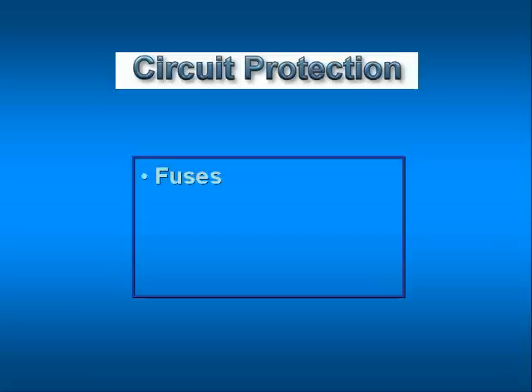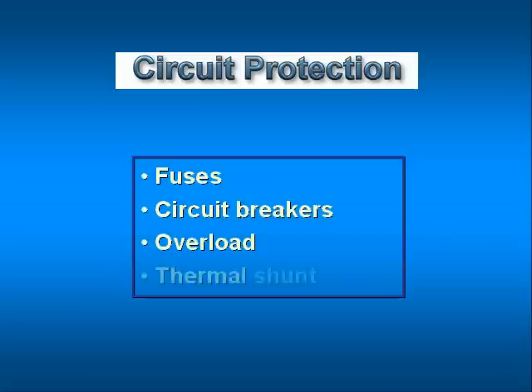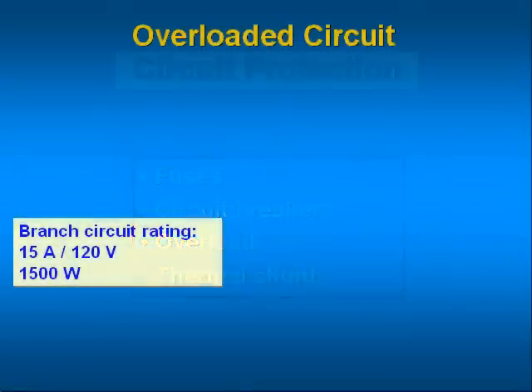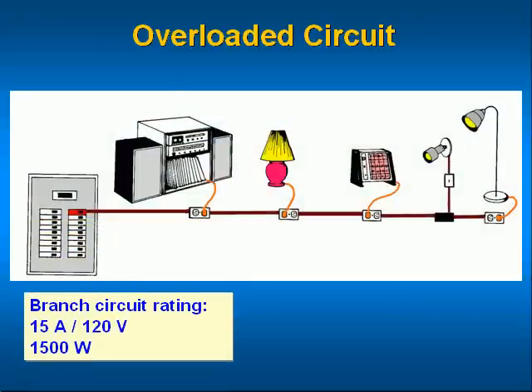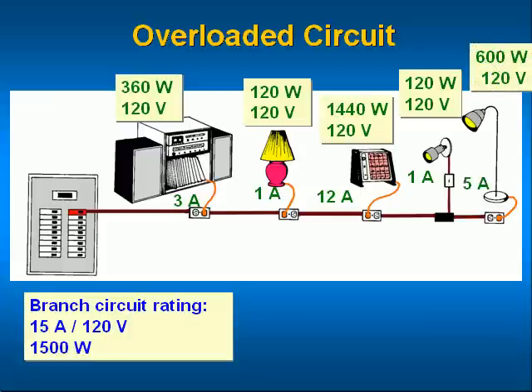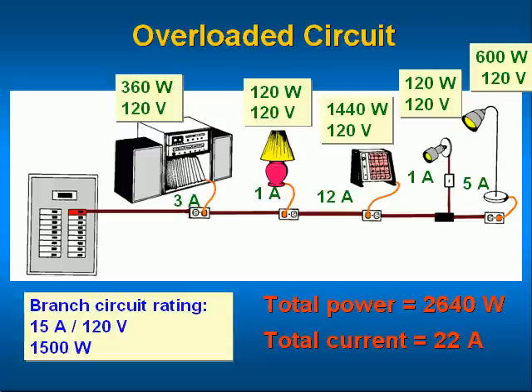Circuit protection involves using protection devices, the proper loading of a circuit to avoid overloading, as well as taking care to avoid shorts. There is a distinction between an overloaded circuit and a short circuit. An overloaded circuit is one in which there is more current being drawn by the circuit than the circuit has been designed to provide. A short circuit is one where the current is taking an unintended and undesired path to ground.